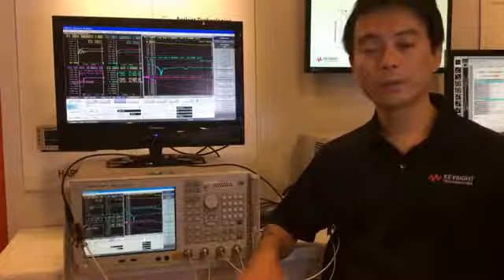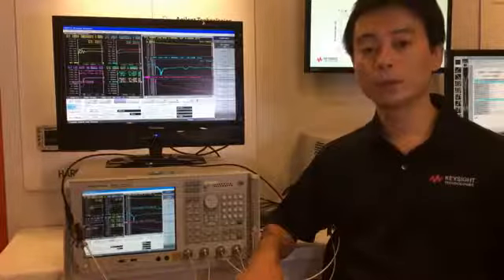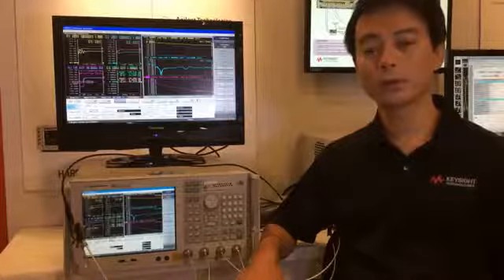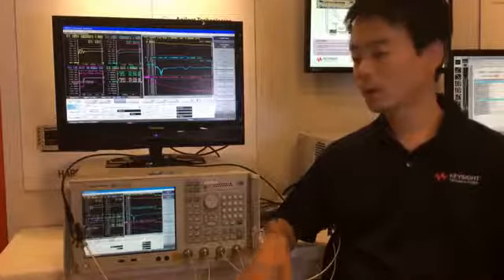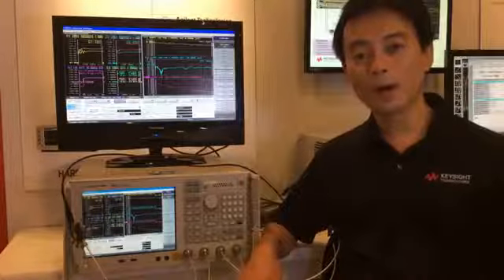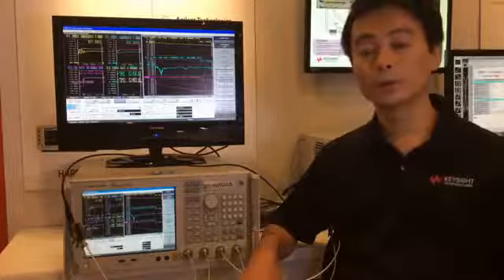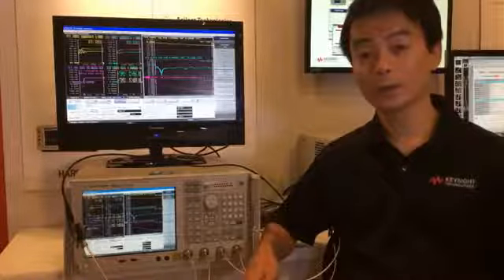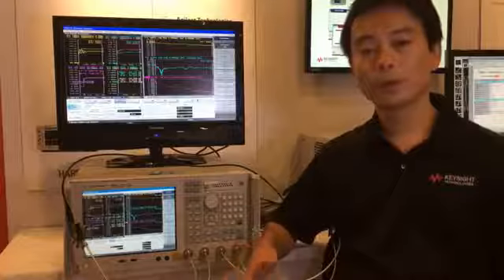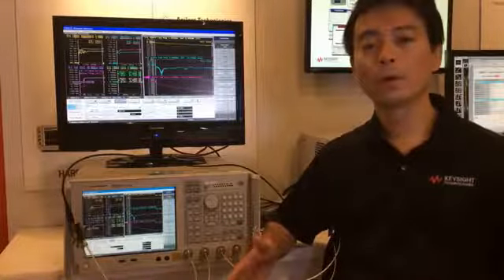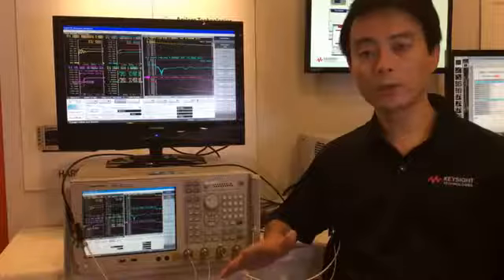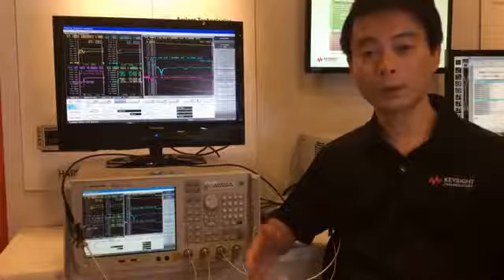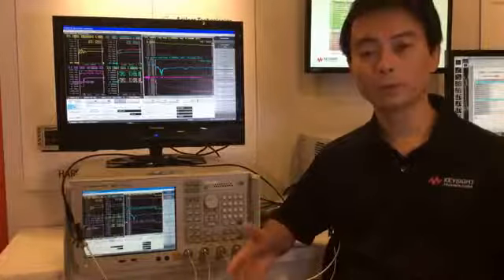The ENA is basically a vector network analyzer to make S-parameter measurements such as S11 and S21 in the frequency domain. Based on this platform, we added a function called TDR to perform time domain analysis. So the ENA with Option TDR can make both frequency domain measurements and time domain analysis very fast and accurately as a one-box solution.